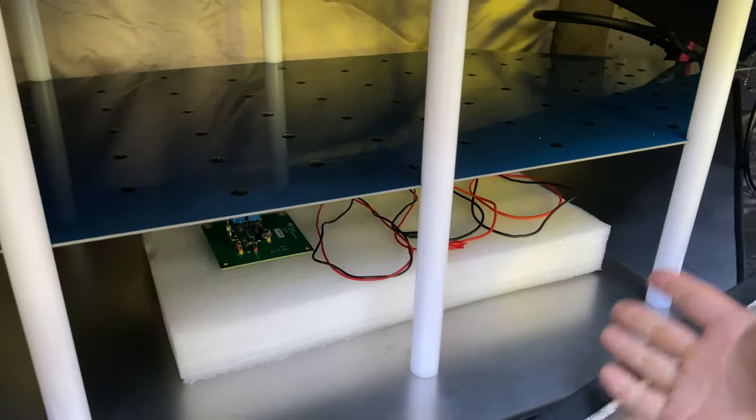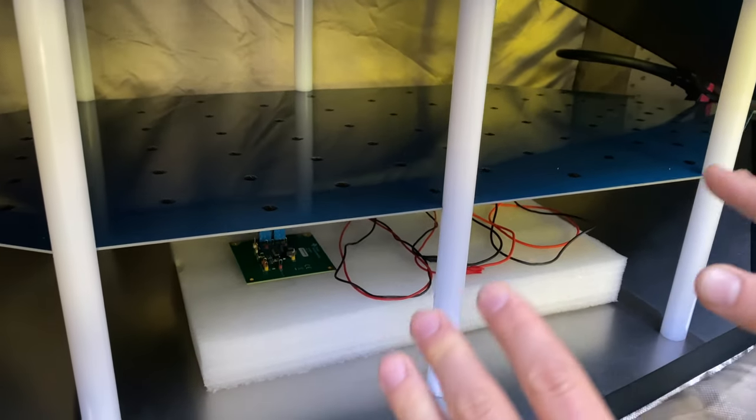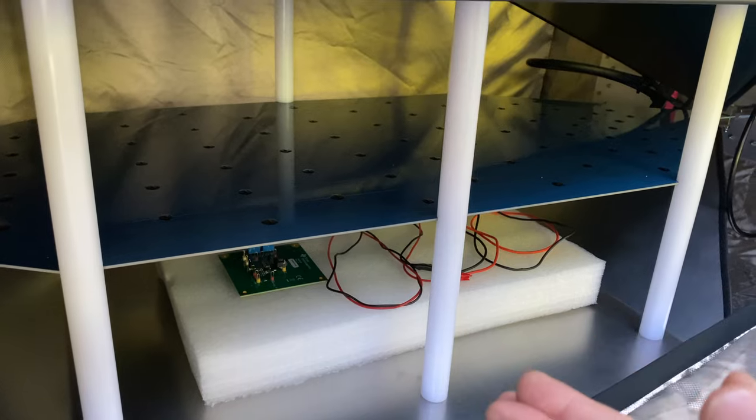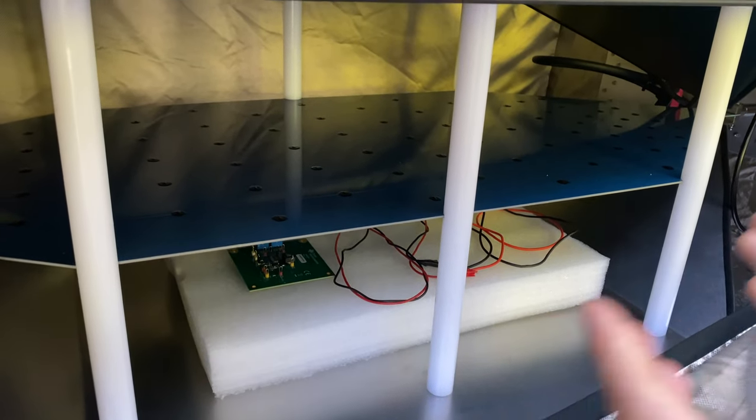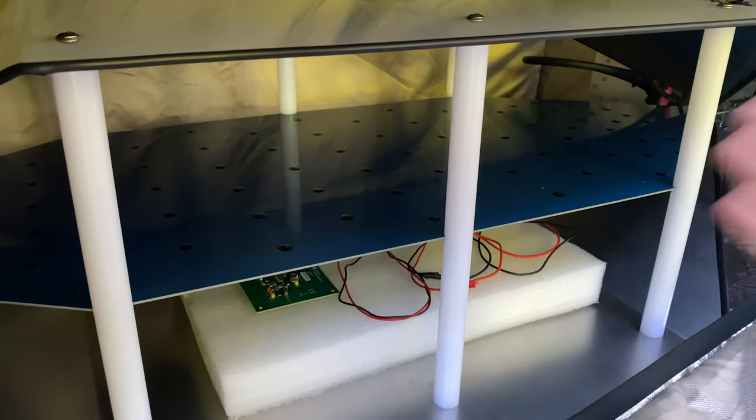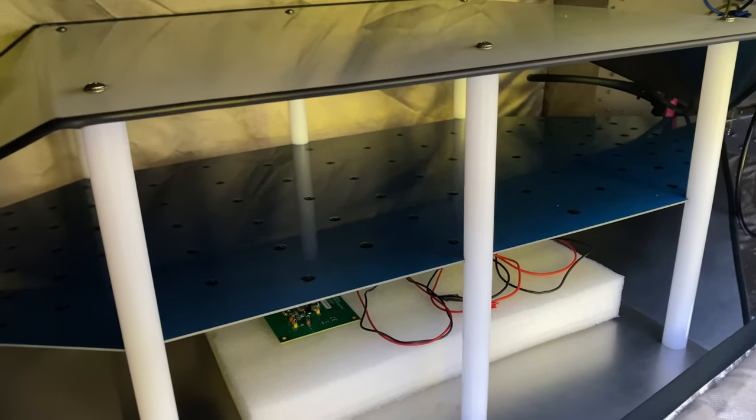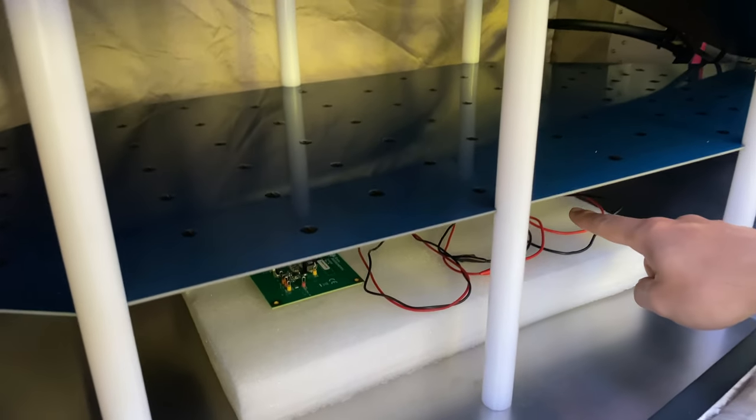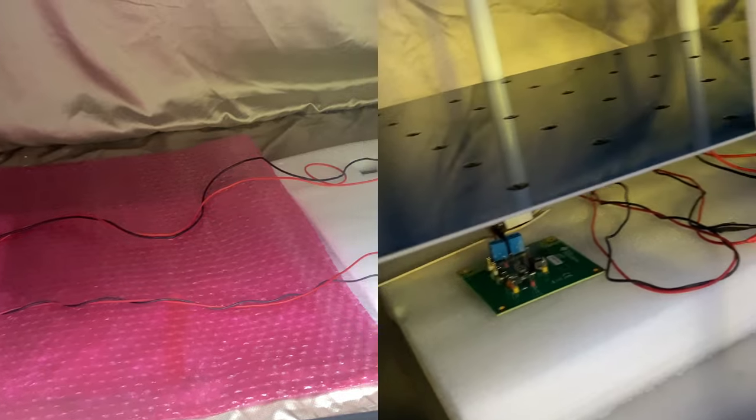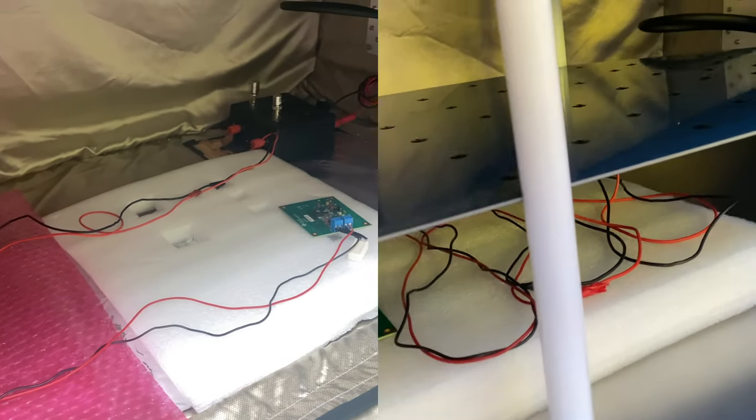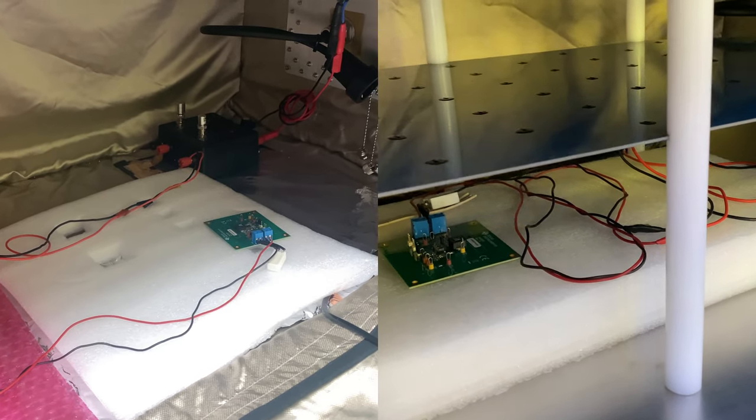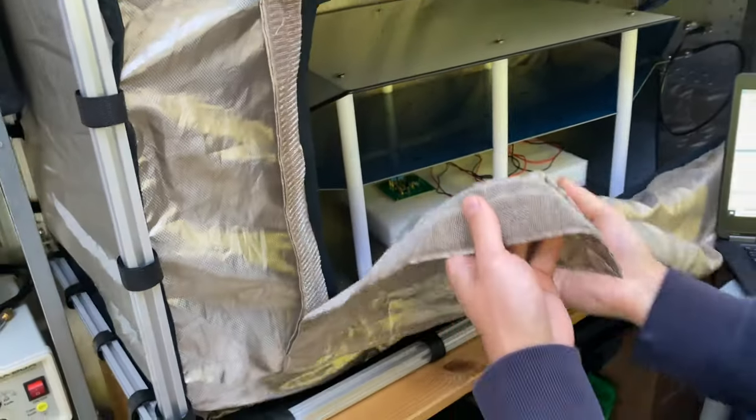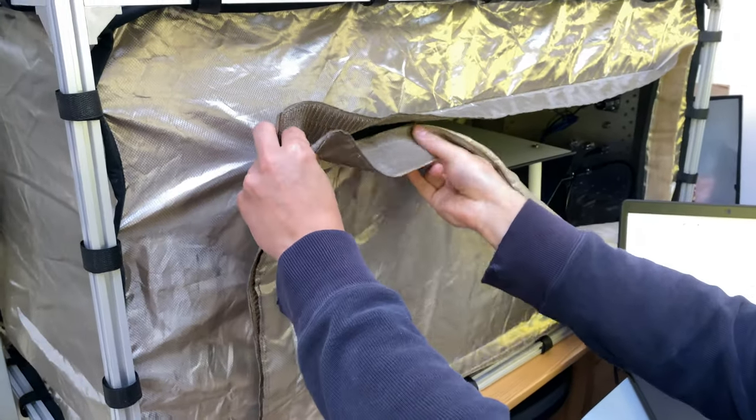Of course, this would affect the radiating emission if we compare the results with a test house result, which they use a straight cable. But we will just see how close with this setup compared to the test house setup. I have to point out that behind the wire, we connect the DUT to two LISNs, and the LISNs are both terminated with 50 ohm resistor. So once we set it up, we close the tent and we are going to do a scan.